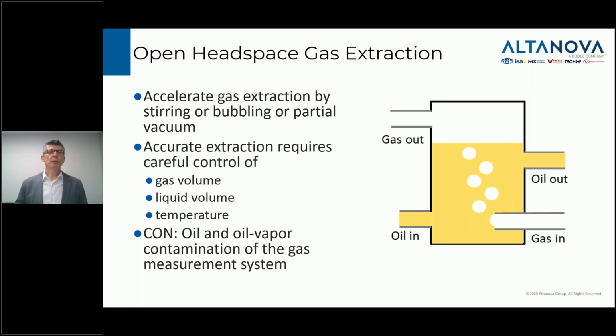And for me, there are really 2 different classifications of gas extraction. One is what I call open headspace. What I mean by that is there's somewhere inside the product, there's a container that is partially filled with oil and partially gas space above the oil. And there are different ways of reaching an equilibrium of the gas concentrations in the headspace above that oil. Some of the products use mixing, some of them use a pump to bubble gas through the oil. There's a product that actually pulls on the oil to create a negative pressure in the headspace, a partial vacuum in the headspace. All of these are techniques to encourage the creation of an equilibrium between the oil and the headspace in a timely way, so that measurements can be done in an hourly or so frequency.